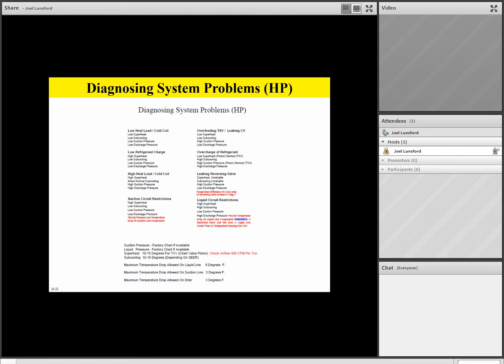In addition, the maximum temperature drop allowed on any of our bi-flow filter dryers will be a 3-degree temperature drop. Any more than 3 degrees, we know we have a restricted dryer. So that'll be a key point when we do our service calls here shortly: if we have a big temperature drop or a big temperature difference across the two cool lines of the reversing valve, we know we have a problem. We know if we have a big temperature drop across a liquid filter dryer, that dryer's got a problem. So be looking carefully for temperature differences across filter dryers, the liquid line itself, the suction line, and the reversing valve. These are all important key things.